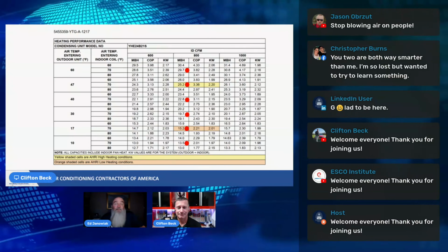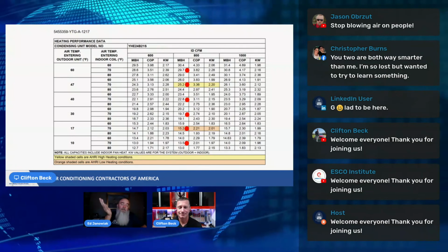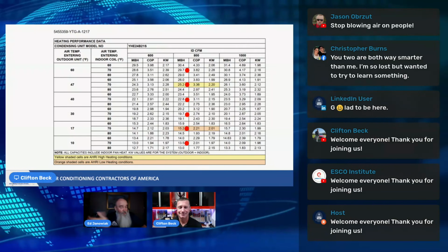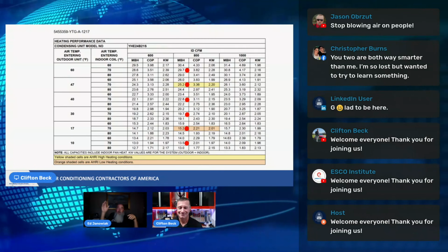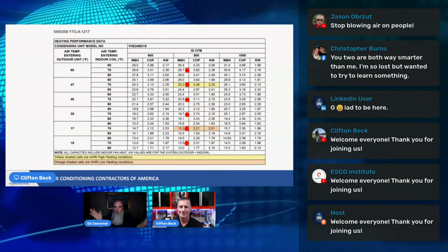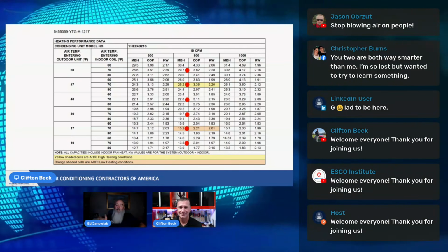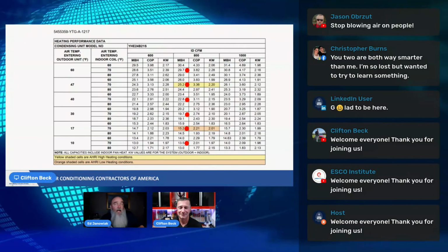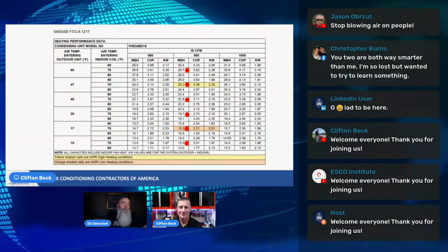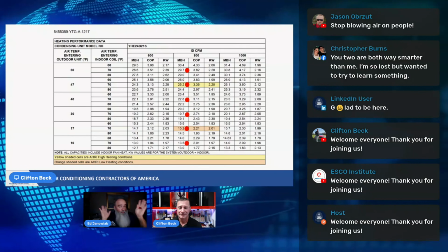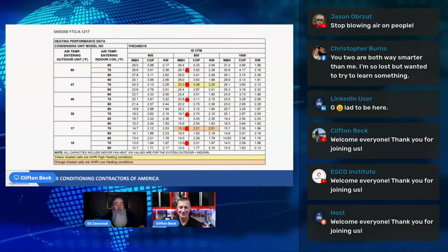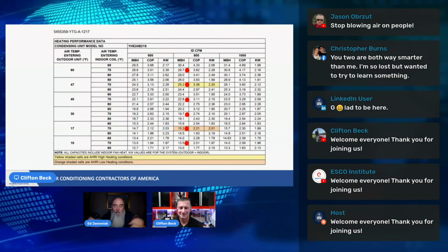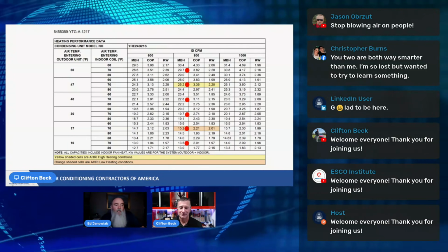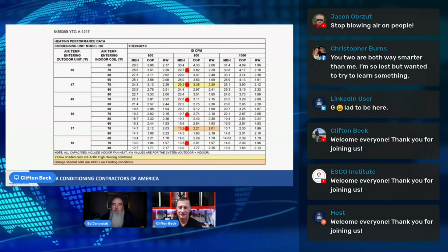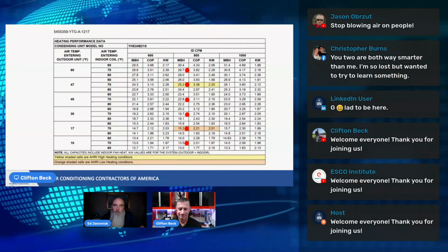So I'm just going to throw it out there that manufacturers for heating, just like for cooling, will generally publish 350, 400, and 450 per nominal ton. You get the most heat out of the highest airflow. And I think that's why, and it's a rule of thumb because I can't find anywhere else to apply it or where it came from. That's why we see that 450 CFM per ton number associated with heat pumps.